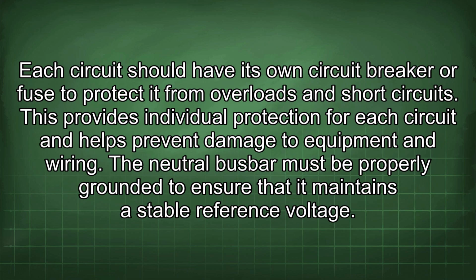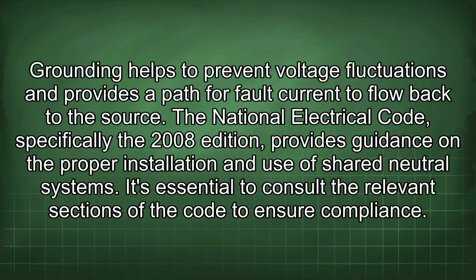Each circuit should have its own circuit breaker or fuse to protect it from overloads and short circuits. This provides individual protection for each circuit and helps prevent damage to equipment and wiring. The neutral busbar must be properly grounded to ensure that it maintains a stable reference voltage. Grounding helps to prevent voltage fluctuations and provides a path for fault current to flow back to the source.